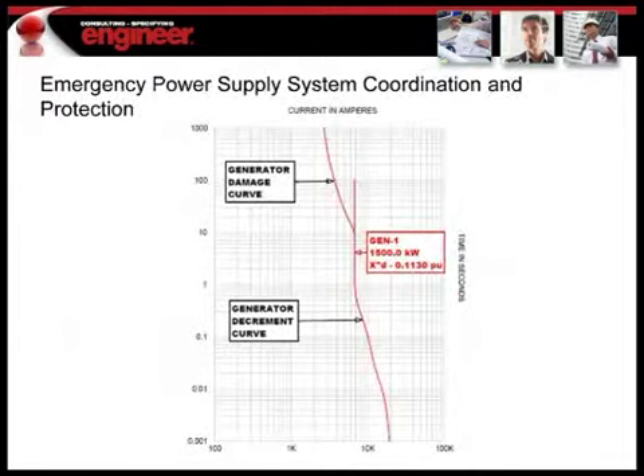Here is the first model that we're taking a look at, the generator. If you look, we're starting at 0 seconds, as low as possible. That's the decrement curve. If you remember from our little calculation, this is the same exact engine that we did our little short calculation on, which is the full load amps of the generator divided by XD double prime. And we got about 20,000 amps. So if you look here, you see 10K, and then the next line will be 20K. So this is actually starting out at right about 20,000 amps. So that would be lining up exactly with what we had calculated by hand.